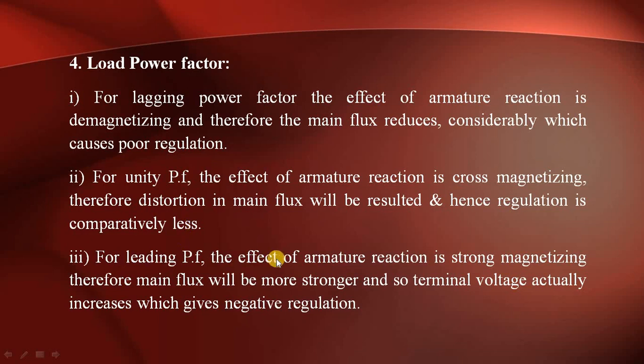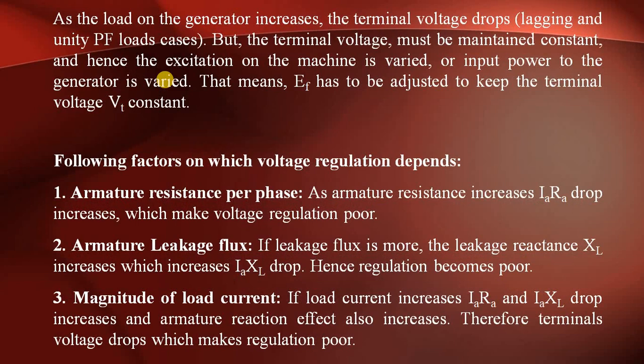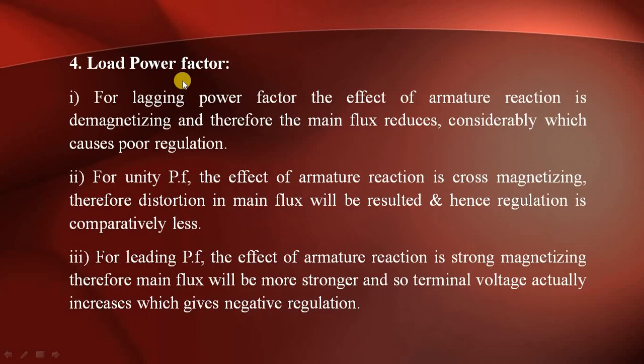The fourth factor is the load power factor. For lagging power factor, the armature reaction has a demagnetizing effect, which reduces the terminal voltage and gives poor regulation. For leading power factor, the armature reaction effect is magnetizing, strengthening the main flux, so the terminal voltage actually increases, giving negative regulation.